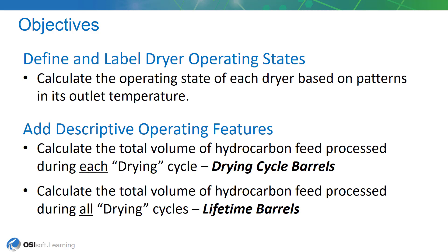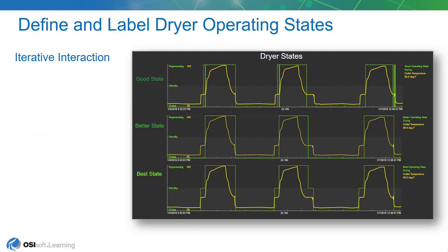The next step is to define and label the dryer operating states, and we're going to take an iterative approach to this. In the trend, you can see three traces — the yellow traces are the outlet temperature of one of the dryers. What we'd like to do is identify the regenerating state as the time that temperature rises. The green trace shows the results of our analytic that will identify the cycles for each dryer.